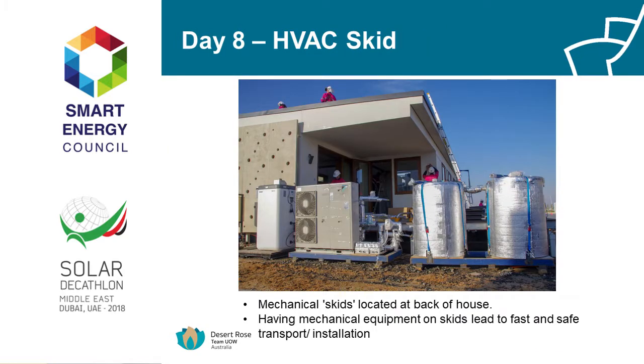We also installed what's called our mechanical skids. These three units pick up and slide nicely into the container, containing our hot water unit, outdoor heat pump, air conditioning unit, and our PCM tanks. These phase change material tanks acted like a thermal battery - we use our air conditioning system to charge them, filled with water and a phase change material, charging during the night when the air conditioner runs at higher efficiency, then discharging that cool water during the hot Dubai days to run our system.